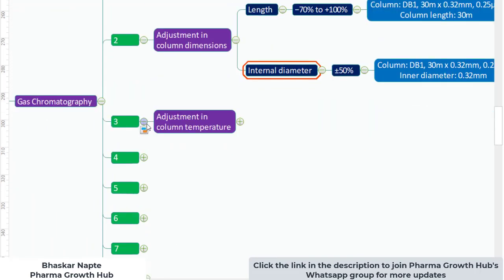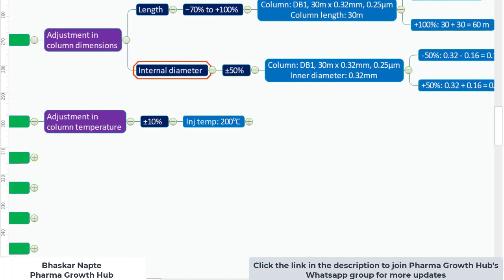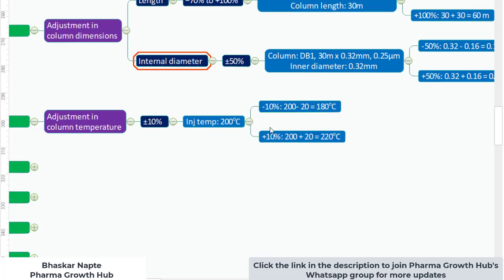The third parameter is adjustment in column temperature. Column temperature can be adjusted by plus or minus 10% — note that it is 10%, not 10 degrees. For example, if the injector temperature is 200°C, minus 10% gives 180°C and plus 10% gives 220°C.